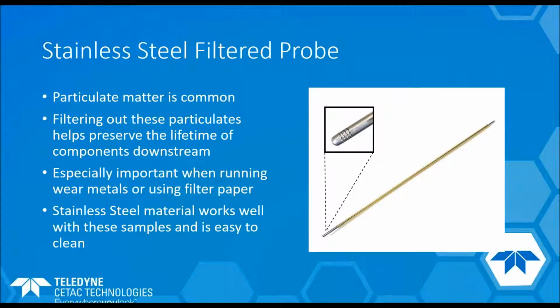And because the filter's on the outside of the probe and not something internal, you can't get blockages that get caught up against the filter to block the entirety of the probe. This design has been in beta testing and has done very well. We recently updated it to use slightly larger filter holes, and the latest version is going to be released within the next month or so.